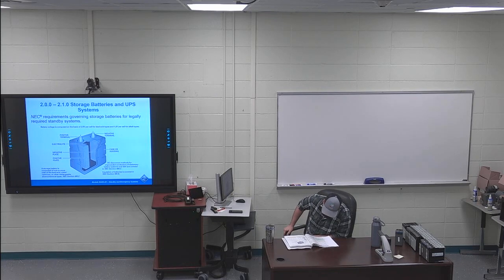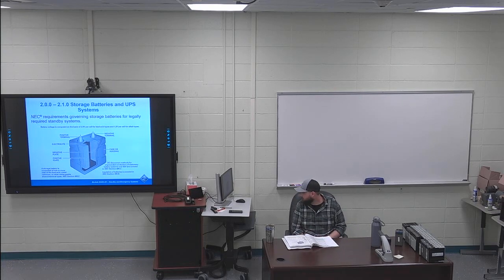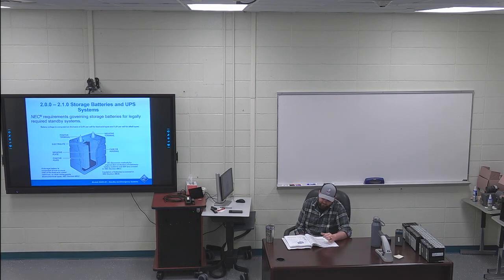I've got just the first sentence in 210 highlighted. NEC section 701.12(C) specifies that a storage battery of suitable rating and capacity is required to supply and maintain at least 87.5% of the system voltage for the total load of circuits supplying legally required standby power for a period of at least 1.5 hours. When I was going through this chapter, they hit those numbers pretty hard. You need to know that 87.5% of the system voltage, and that it needs to be able to run for at least 1.5 hours. So keep those in mind, the 87.5% and the 1.5 hour required run time.